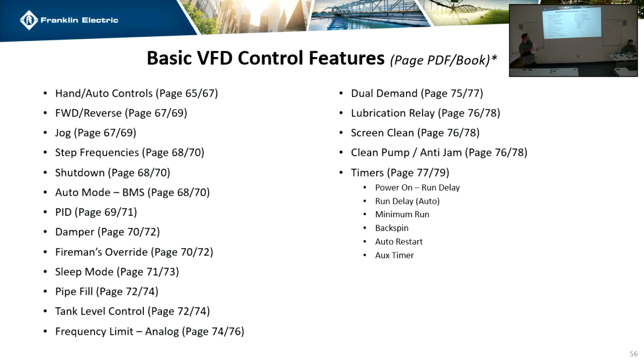All right, so forward reverse is page 69. This is also where you go to see how to wire start stop. This section is for a drive by itself. This is not how you would wire a start stop if you have an HOA switch. It's different. For an HOA switch, you have to replicate this inside of your relay, basically. The 1 and 2 or the FE, FS, that's where you put your start stop. So if you have just a drive, you can come here. It'll show you how to wire it and how to program it.